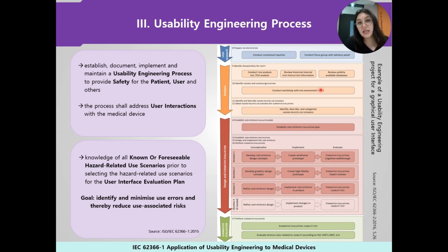The usability engineering activities for a medical device shall be planned, carried out, and documented by personnel competent on the basis of appropriate education, training, skills, or experience. Very important here is that everything should be documented so that you can look at the documentation later on and find the same objective findings as you did the first time.